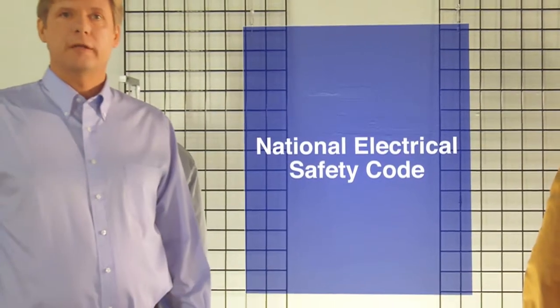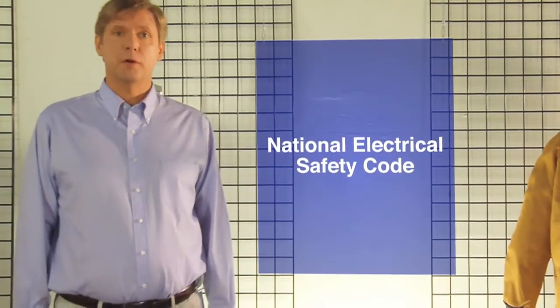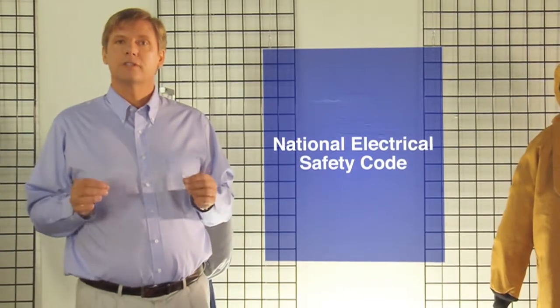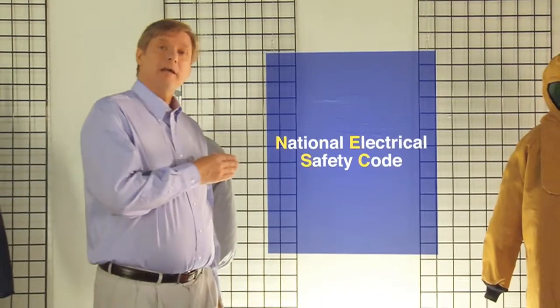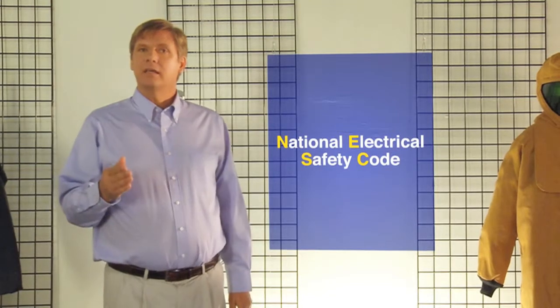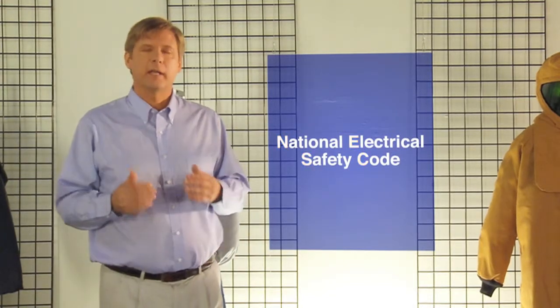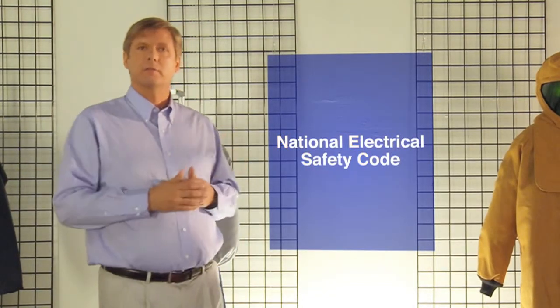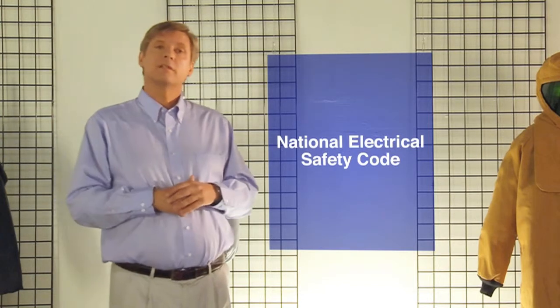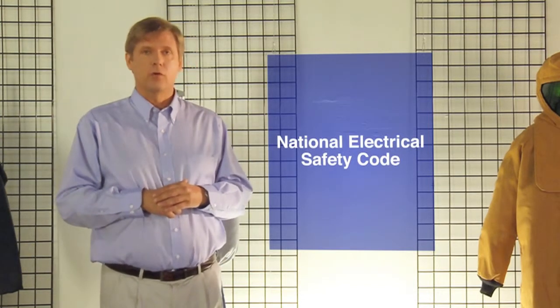Utilities have their own standard to protect their workers from arc flash exposure. It is the National Electrical Safety Code, or NESC. NESC covers utility facilities and equipment up to the service point of its customers. After that point, the requirements of NFPA 70E take over.